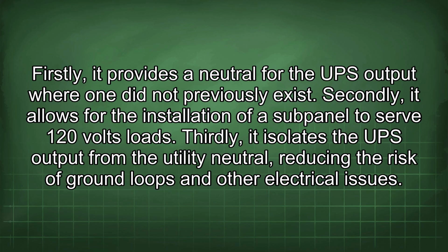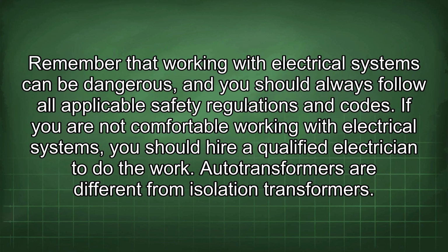Firstly, it provides a neutral for the UPS output where one did not previously exist. Secondly, it allows for the installation of a subpanel to serve 120 volt loads. Thirdly, it isolates the UPS output from the utility neutral, reducing the risk of ground loops and other electrical issues. Remember that working with electrical systems can be dangerous, and you should always follow all applicable safety regulations and codes. If you are not comfortable working with electrical systems, you should hire a qualified electrician to do the work.